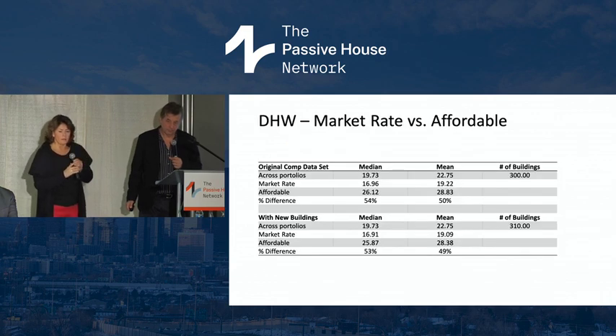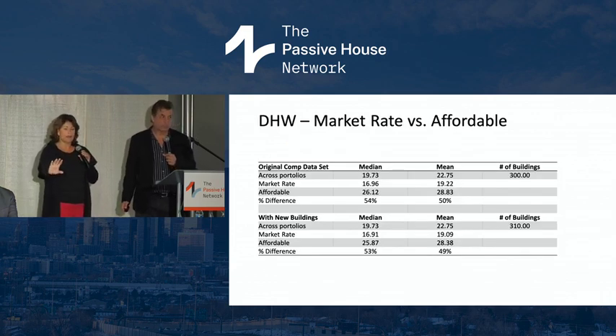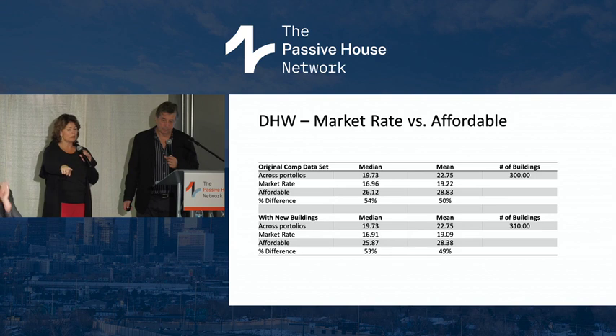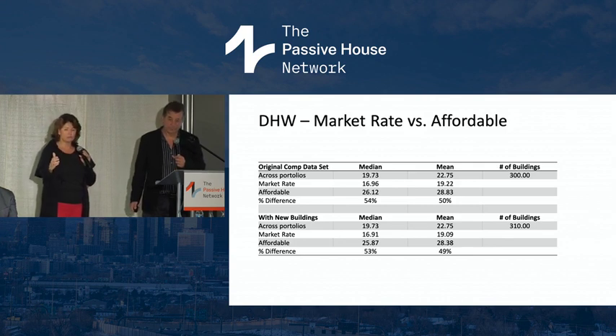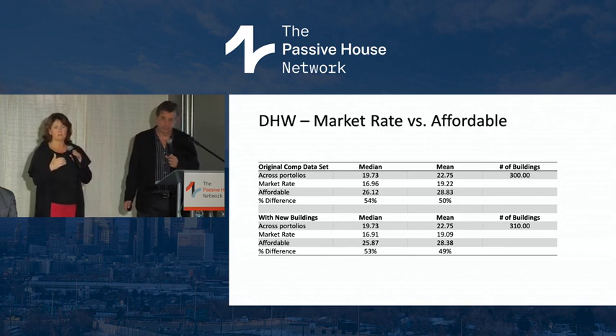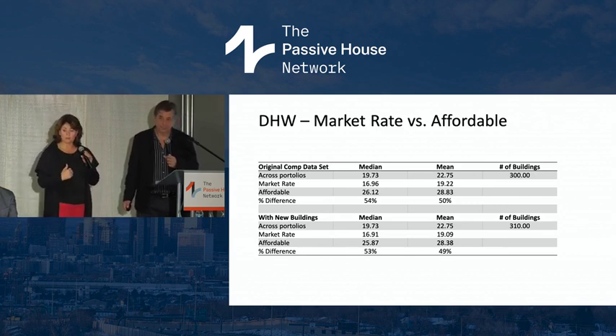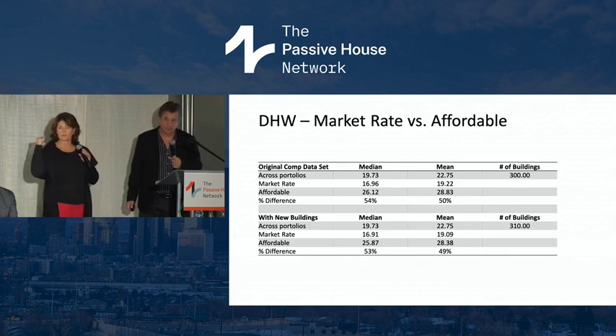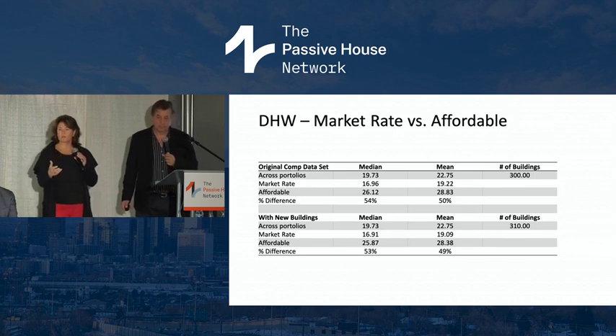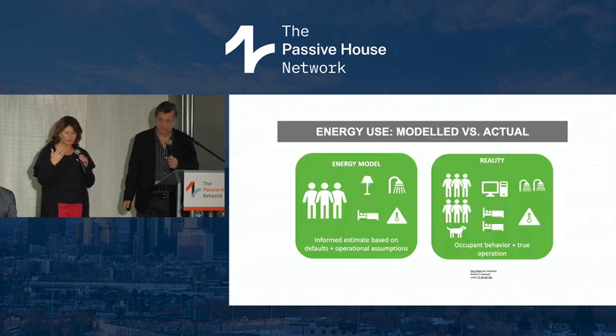Okay, next step - this is just all of that data in a table format. What I'm showing here is, if you look at the original comp set, which is the first 4 lines, the difference between the market rate average EUI per square foot for domestic hot water and the affordable median EUI is 54%. If you choose the mean, it's 50%. So they're using 50% more domestic hot water in affordable housing. When we add in our new buildings, our 10 new buildings, it's very similar, 53% to 49%. So the strides in domestic hot water use have not really happened in the supply system - the heating element, even though those are much better, we're still dominated by circulation losses and end user cooking, cleaning, all of that.